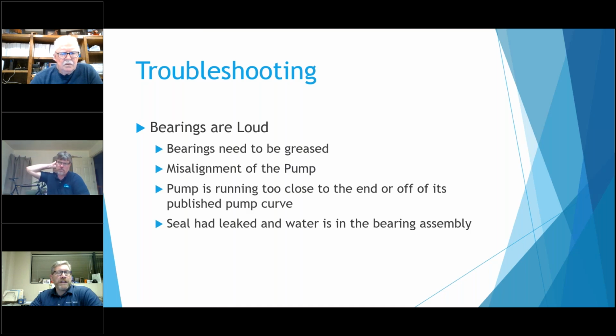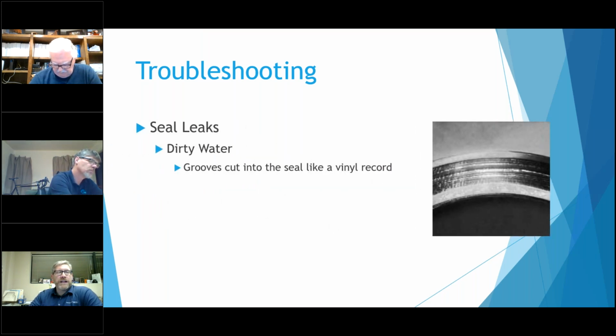Some of the things like bearings are loud. Sometimes they just need to be greased, but misalignment certainly can cause that, or if it's running towards the extremes of the curves, that can cause those issues as well. With seal leaks, I always try to caution people not to just throw away the seal if you have problems with it. A seal that's failed can kind of tell a story.